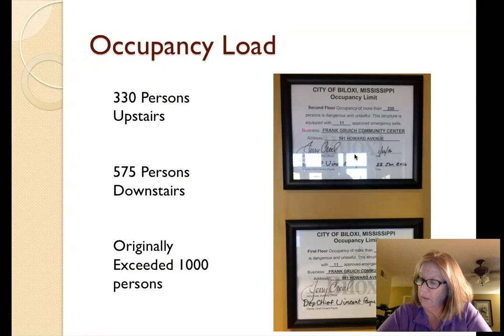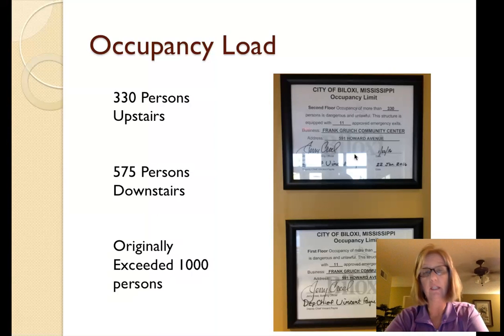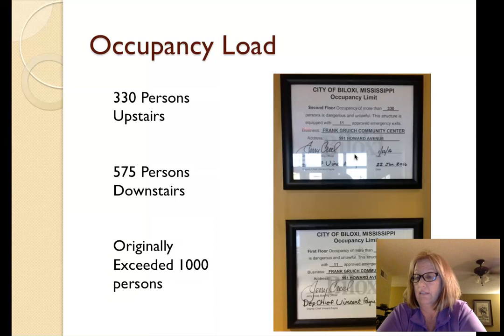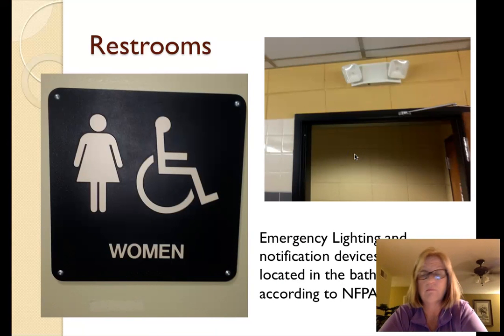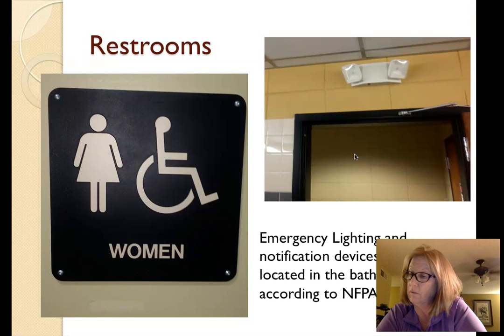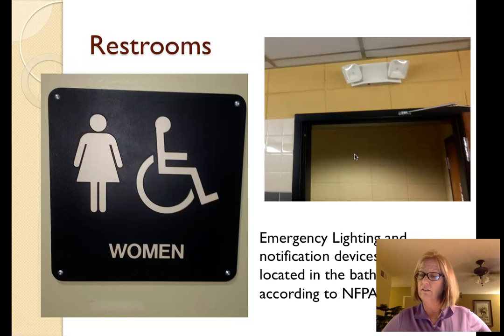The occupancy load was posted at the front, and it contained 2 floors. The first floor was for 575 persons, and the second floor was 330 persons on the upstairs part, and was showing 11 emergency exits. Originally, this building had an occupancy of over 1,000 persons, and so by International Fire Code, the building had to contain a fire alarm, sprinkler system, and a voice activation evacuation system. The restrooms also had strobe and fire alarm notification devices inside the rooms and emergency lighting, and this is in accordance with NFPA 70 and 72.